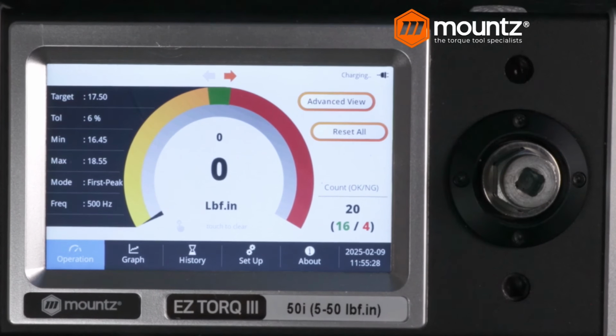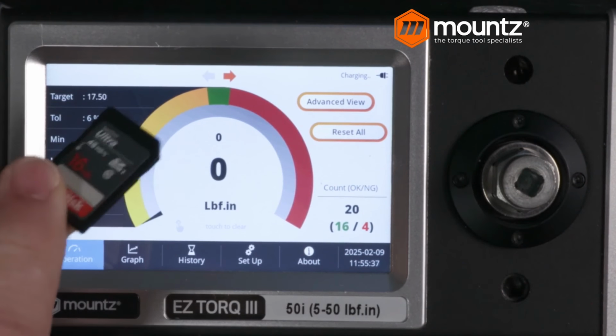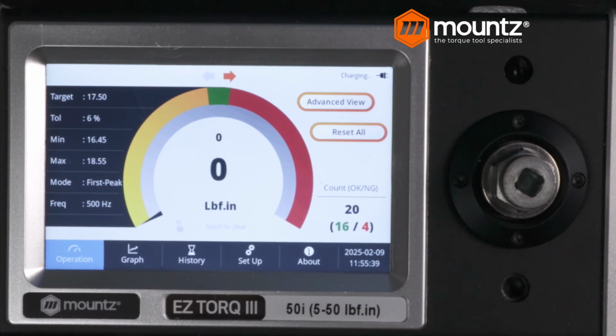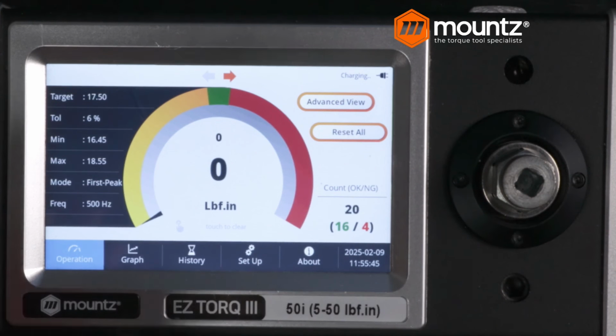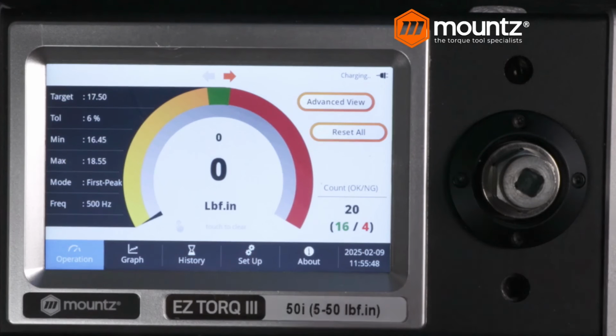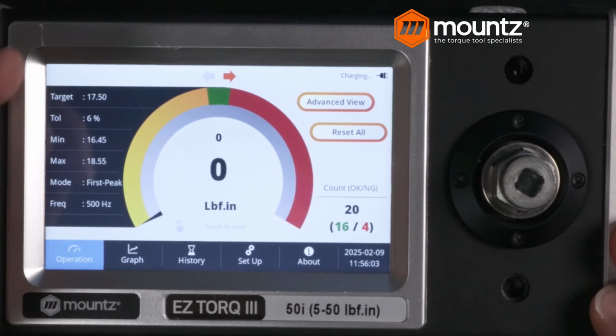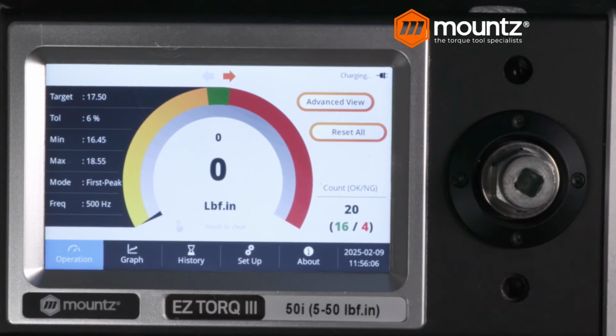And then we also have an SD card that is located in the controller, and we can then go ahead and save all of that data on the card, and that information then can be downloaded at a later time. The file structure for these goes by the year, the month, and then the day, and those will give you all of those readings. And then if you are adding a serial number to that, that'll be one of the data fields in the string of text, along with the target, the min, max, all of these readings, plus whatever the value was that you achieved.